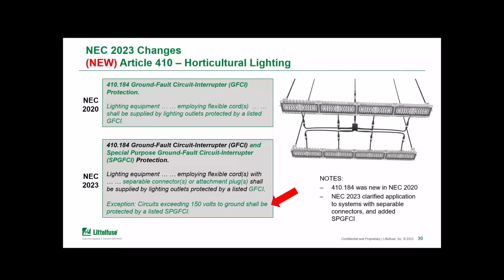The lighting systems use flexible cords and separable plugs, and that provides flexibility in the setup and to be able to expand or modify or move them around as the facility changes and depending on what they might be growing. Now, just for a little bit of history, the requirement for that Class A GFCI protection was first added in NEC 2020. And as we've talked about, this applied to lighting systems that were then 150 volts line to ground and below.